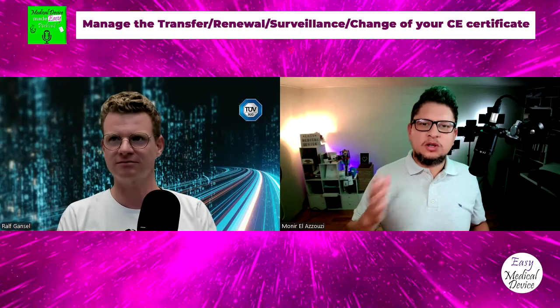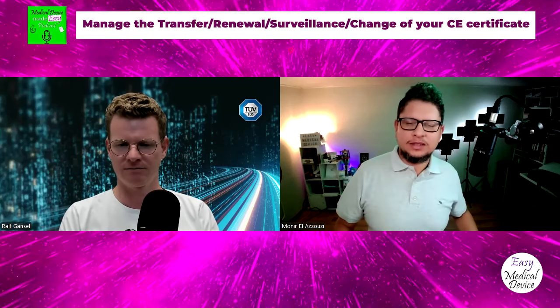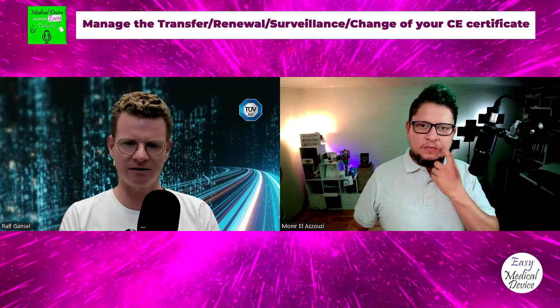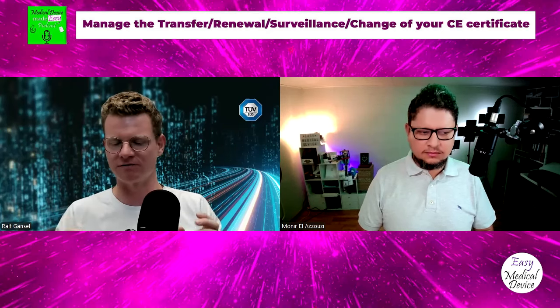Yeah, because we have the creation of the certificate. When you do surveillance one, surveillance two, etc., you are not checking everything in surveillance one or everything in surveillance two. It's a cycle. So during this cycle, you have to check everything, but you can divide it among the different surveillance audits. Exactly. So the client or the manufacturer will receive an audit plan with different chapters. They look into these chapters in this year's audit, and in the next surveillance audit, they follow up with the missing chapters from the MDR and the ISO, so that in general, both surveillance audits and one recertification audit cover everything.